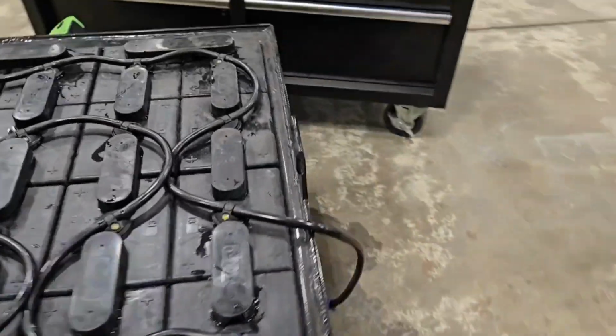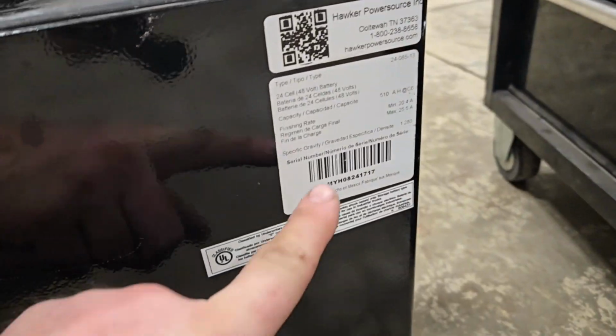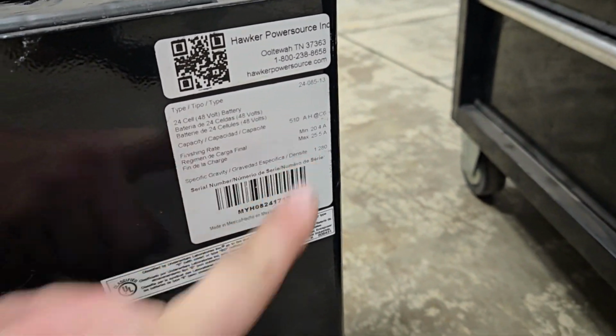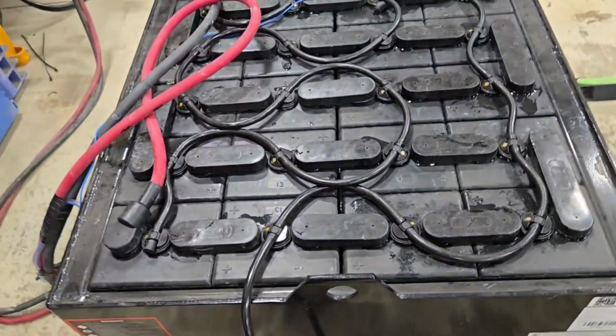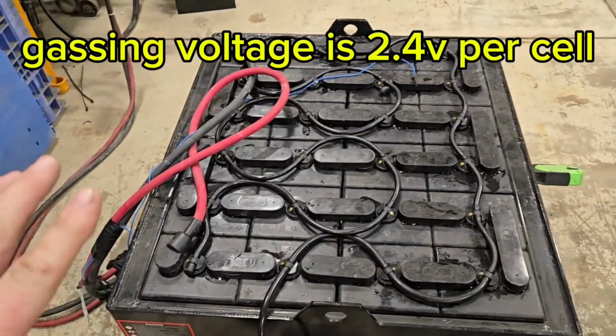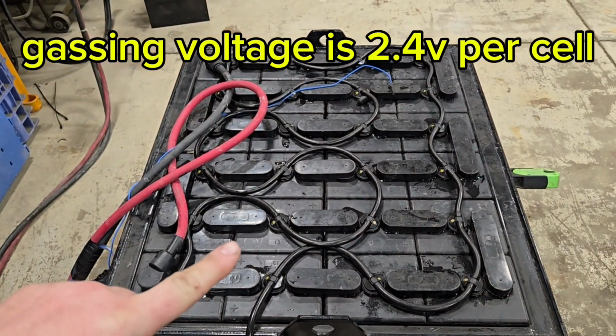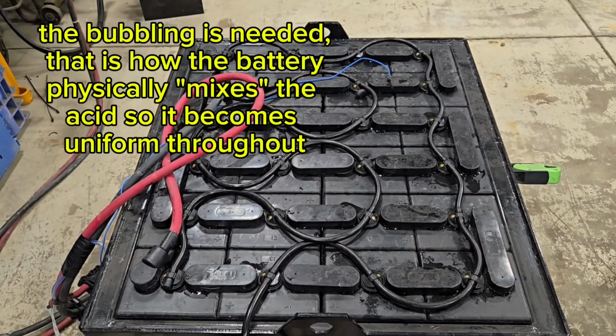It will hold 25 amps for a specified amount of time. I'm doing this because it's AKA the finish rate of the battery, and I need this to run for about 20-30 minutes to come up to gassing voltage, so it will physically bubble inside.